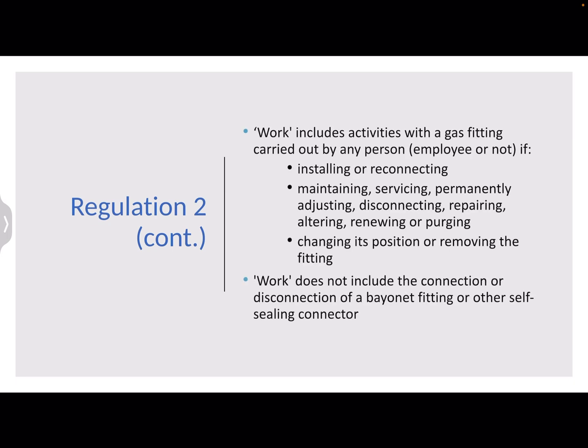Fortunately, regulation two contains your definitions and it contains the definition of work. That says that work includes activities with a gas fitting carried out by any person if they've been installing or reconnecting, maintaining, servicing, permanently adjusting, disconnecting, repairing, altering, renewing or purging, or changing the position of a gas fitting.